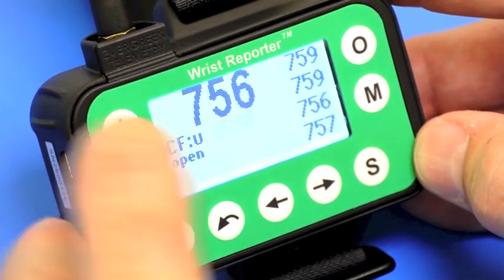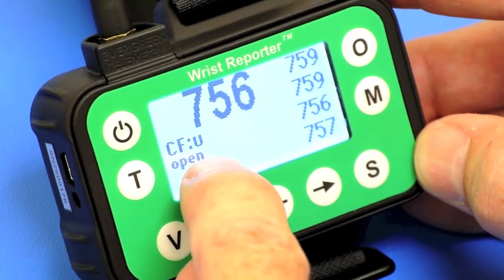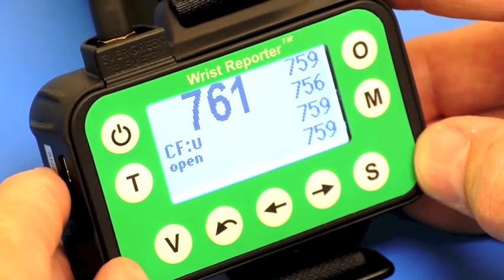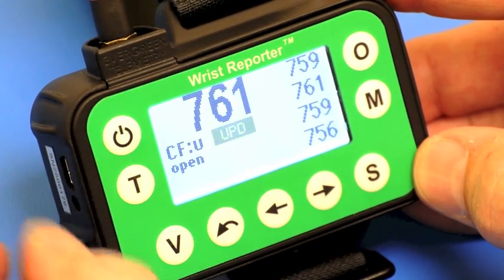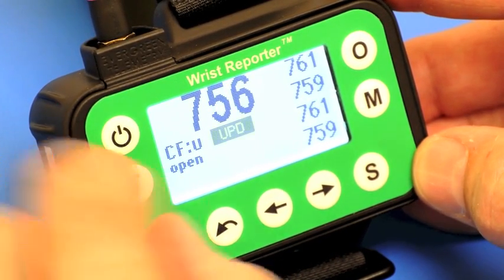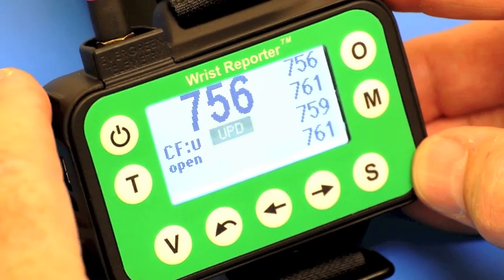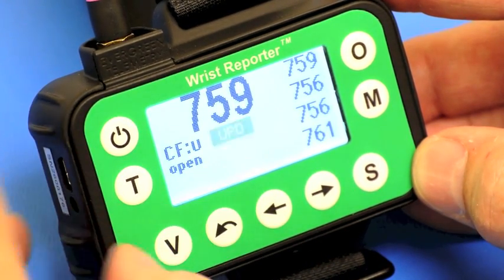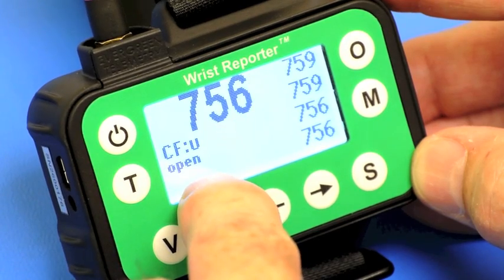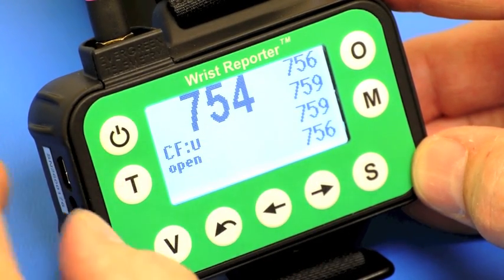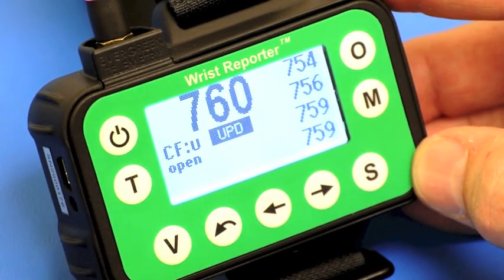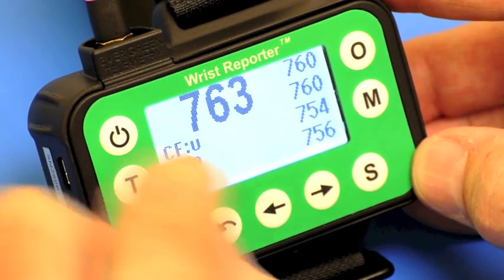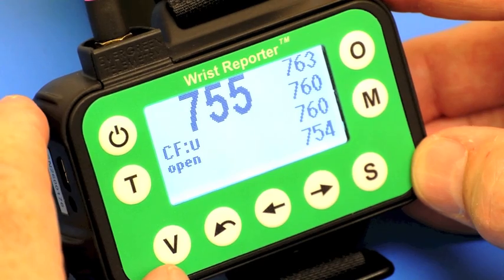In terms of units, we're designating here that we're measuring CFM, and the little 'u' tells us that those are uncorrected readings. Every time the rectangle flashes, that's a new reading coming in. 'Open' means that the flaps are open. If the flaps were closed it would say 'closed,' but you can have a flaps-closed reading that is not back-pressure compensated — especially useful for low flow. The flaps are open and we're measuring uncompensated CFM.